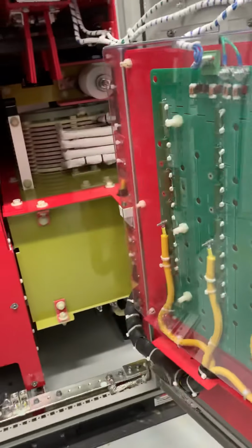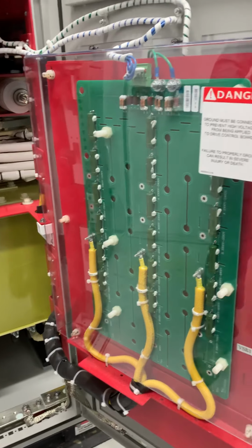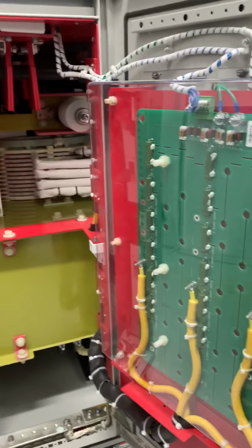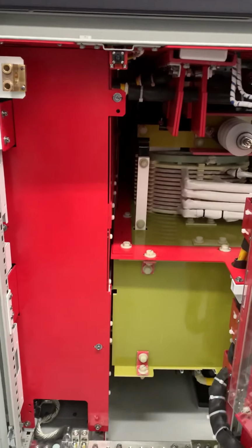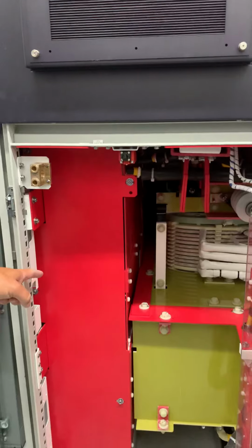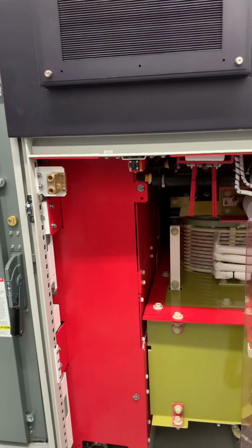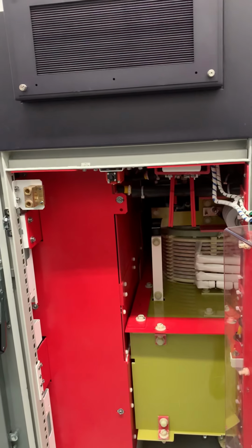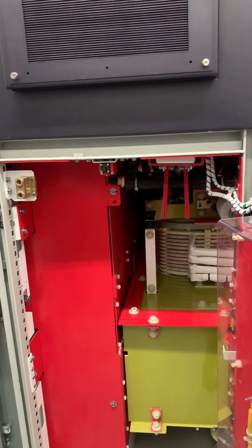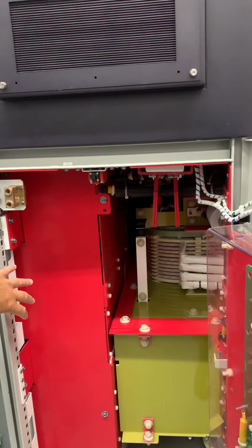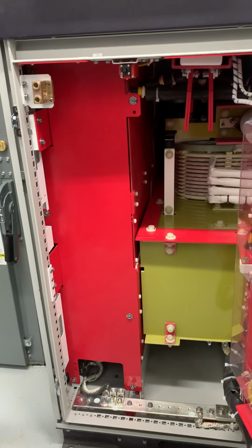That's your voltage sensing board right there. So the information that you're getting and that we're getting up here for the motor voltage is coming from this. Okay. So normally your motor leads would be right back here, but they have those jumpers going up to the top ones that they put up there in the back. Okay. But normally you could just take this cover off, slide it off, and your line and load leads would be right here, if it's bottom fed, but this one's top fed.